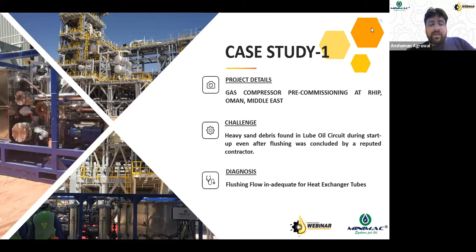So what is the solution? Actually, a special need is required for heat exchanger flushing, because heat exchangers are typical systems which have multiple tubings. Though the tubings are of just 1 inch or 1.5 inch in diameter, they are multiple in number. In a few cases, they are around 200 or 300 in number. And this actually increases the entire flow rate through the heat exchangers.